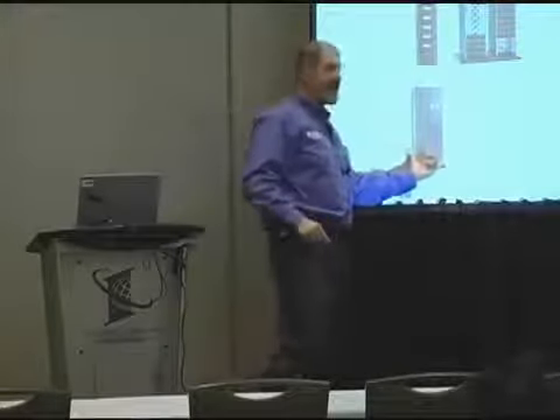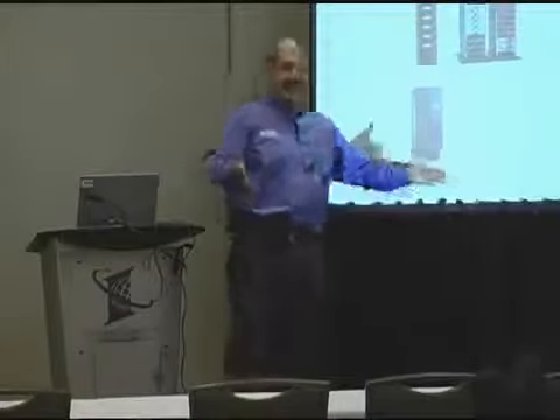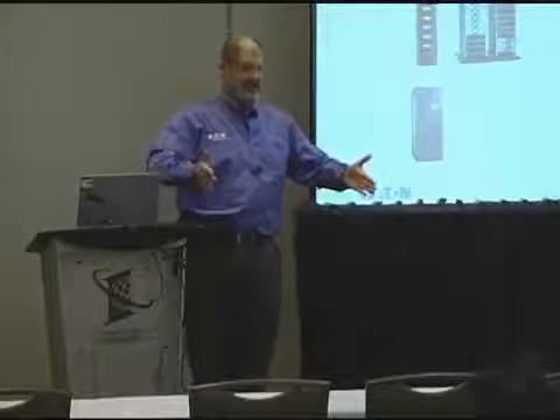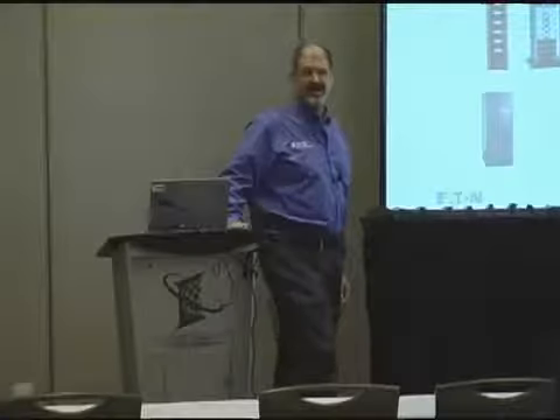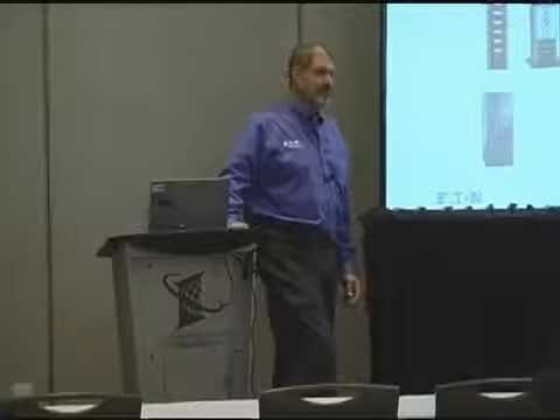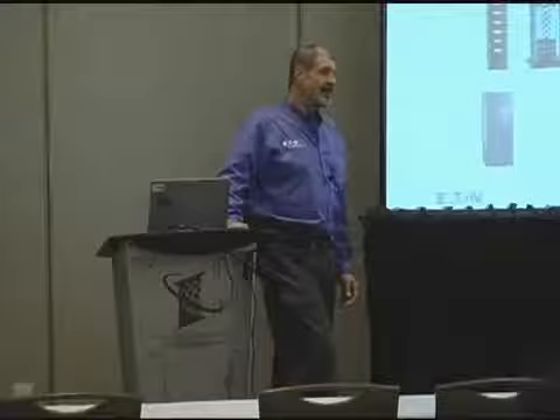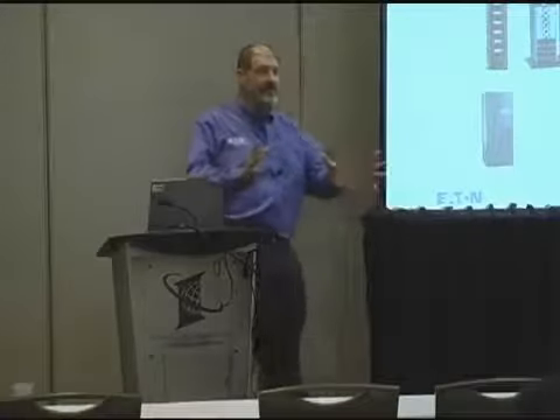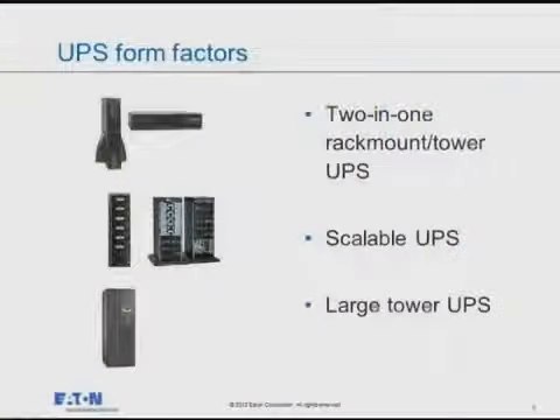Here we're looking at an 80 kVA, which is a 19-inch fridge. When you get into the larger UPSs, they become just bigger fridges. And literally, they're fridges. Each section could weigh up to 4,800 or 5,000 pounds. When you get into a battery cabinet, you have to handle them differently. They're no different. A battery pack is a battery pack is a battery pack. This big battery pack, this little one, or the ones internal to here, it's still a battery pack. It's because of the size, it's bigger, and it brings a whole bunch of different challenges. It's not something you can just pick up and move around.